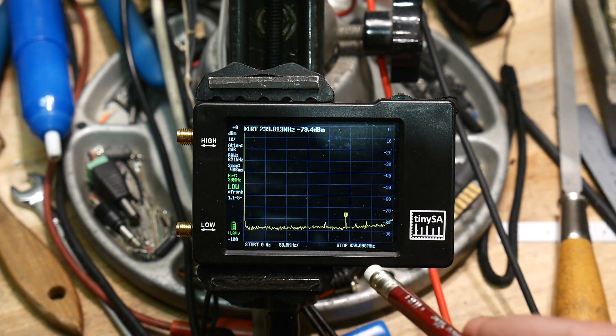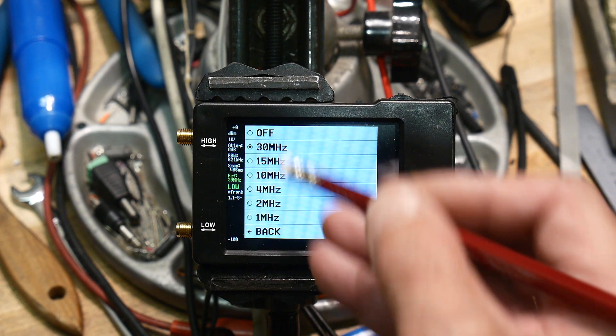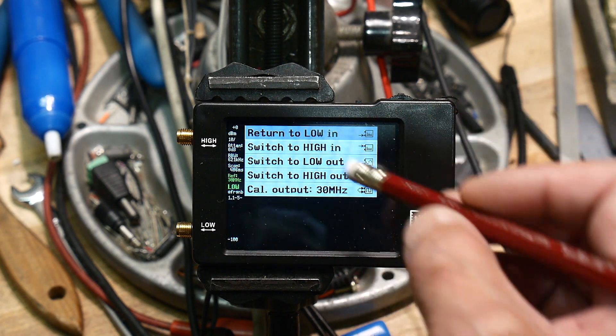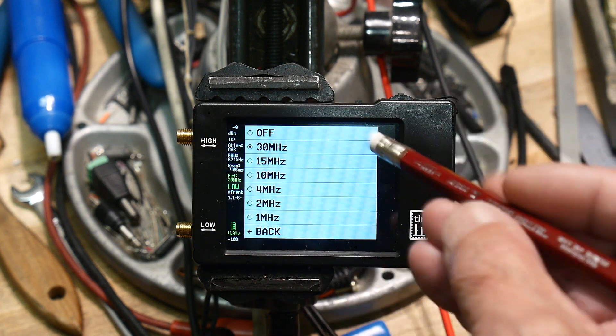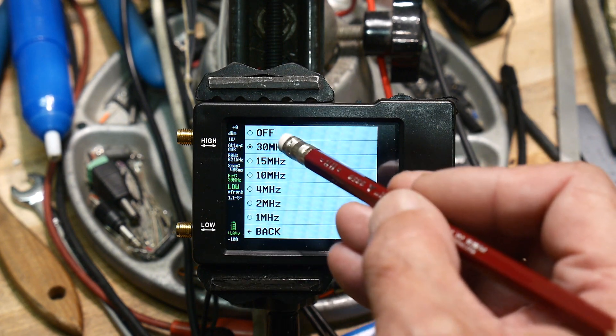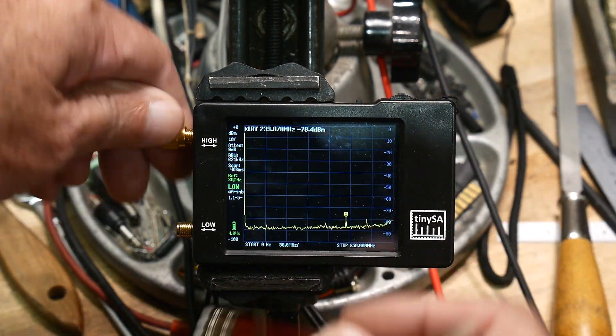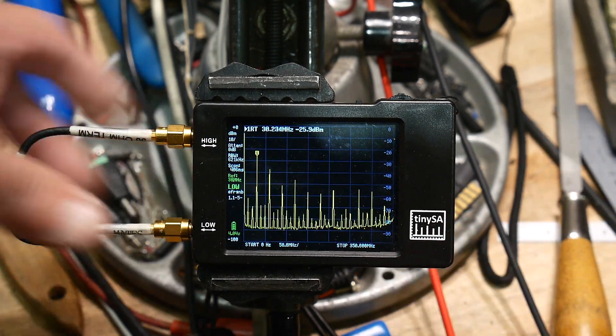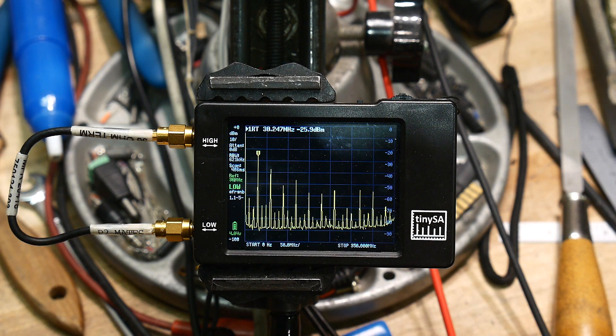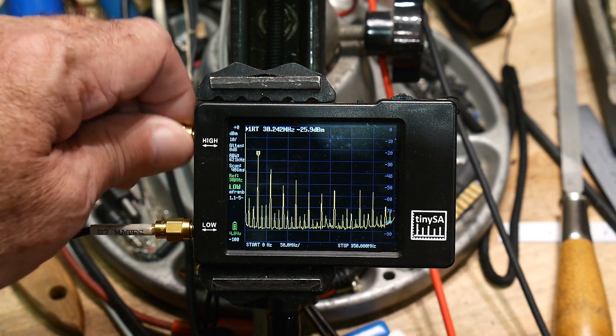So the real problem is going to come with the cal output. You have different options here and you can turn on 30 MHz for the cal. That's coming out the high connector. If you go to take a look at that, everything looks fine on the TinySA. We can connect up the 30 MHz and it's a bunch of harmonics — a bunch of usable frequencies that you can play with and turn on modulation and stuff, a really nice feature. It looks like this is your biggest signal and then it just dies down.